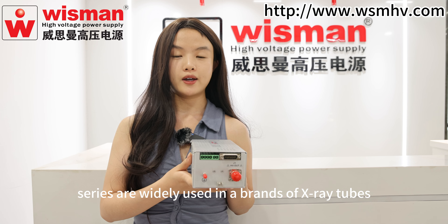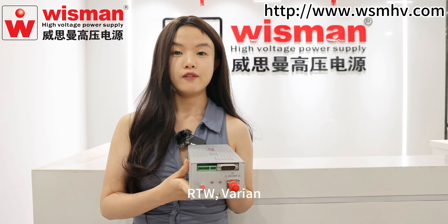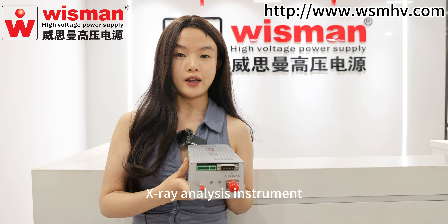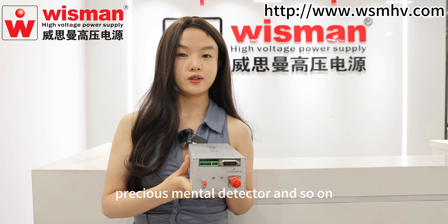The Wisman XWA series are widely used in all brands of X-ray tubes around the world, such as Oxford, RTW, Varian, and so on. Applications include thickness gauge, XRD, X-ray Analyze Instrument, Precious Metal Detector, and so on.